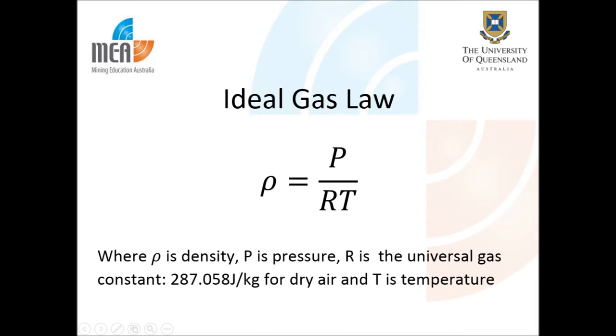Air density for table two is found using the ideal gas law expressed as a function of temperature and pressure, where p is the absolute atmospheric pressure, r is the specific gas constant which is 287.058 joules per kilogram for dry air, and t is temperature in kelvins.